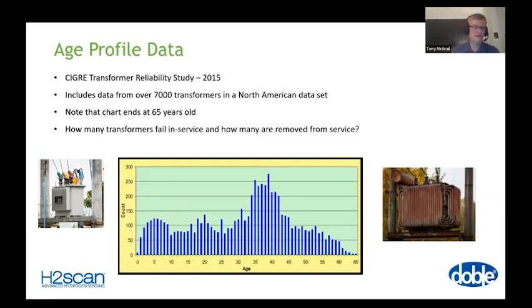One of the questions I sometimes ask is: if I have a transformer which is 1 year old, looking like the one on the left in the picture, and one which is 50 years old, looking like the one on the right, and a full assessment shows they're in the same condition, if I had to choose one, which would I keep? I would always choose the 50-year-old one, because it's only going to get worse over another 50 years, whereas the first one was going to deteriorate over just 1 more year. So after 1 year it's lost a certain amount of its capability, whereas the other one took 50 years to get to the same point. We have to be very careful about how we use age as an indicator of a problem — it's usually an indicator of a failure mode which acts over time.